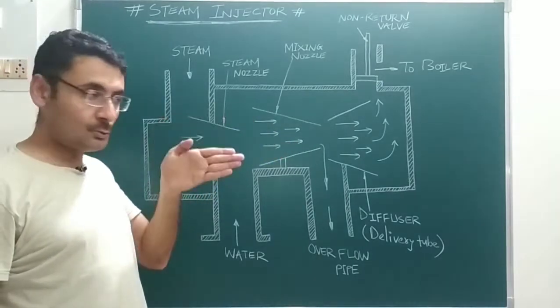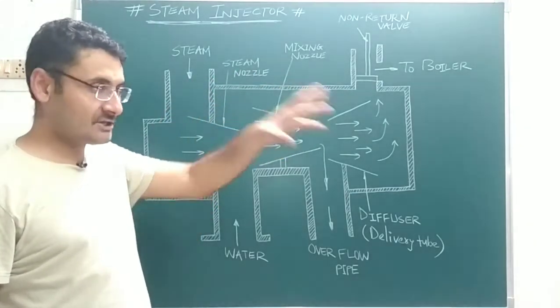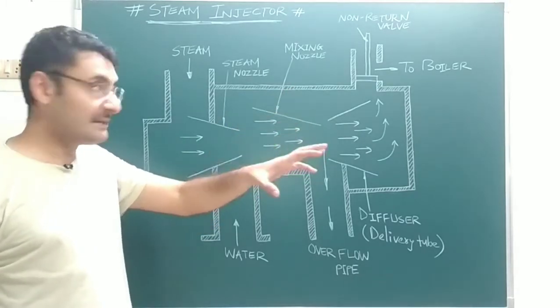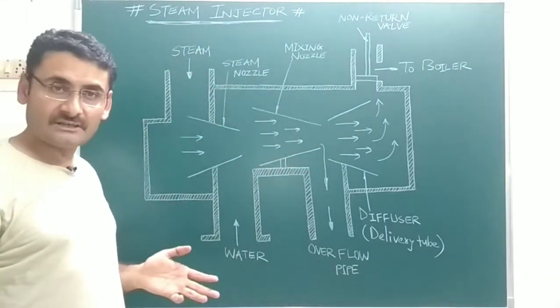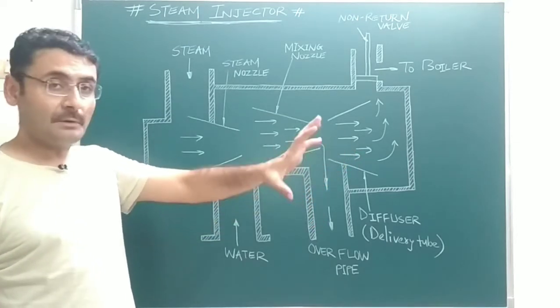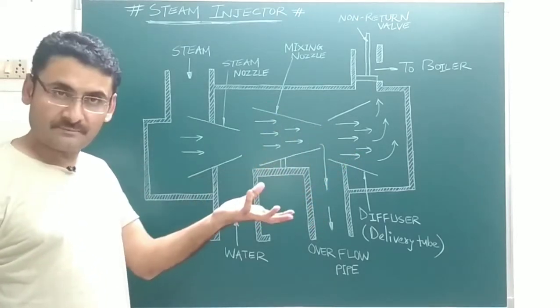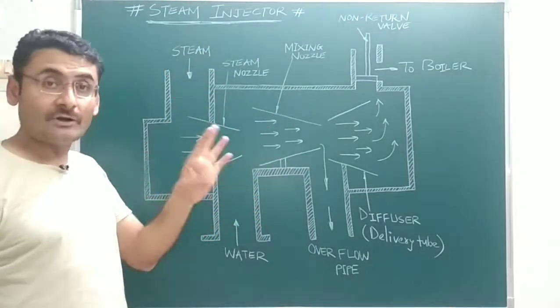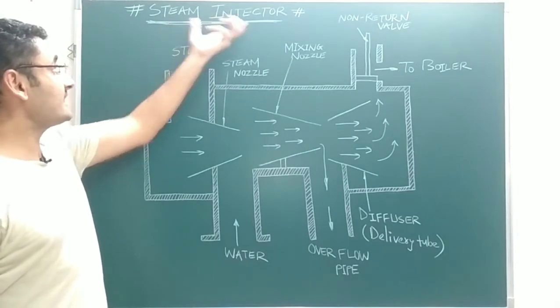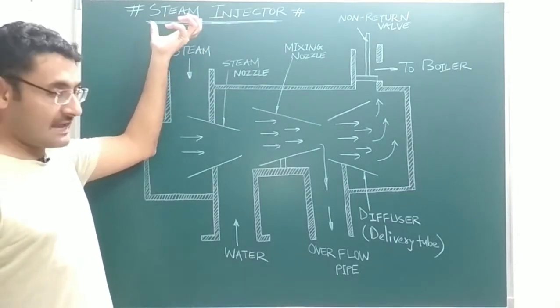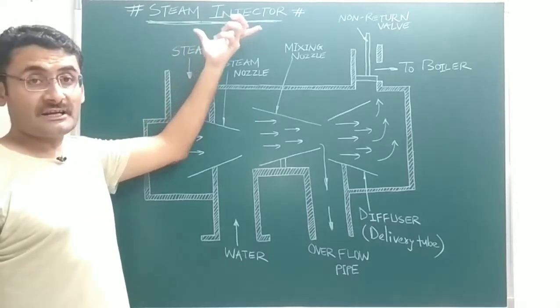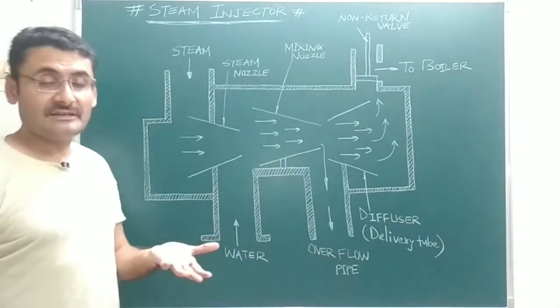Generally, to supply water at high pressure inside the boiler we use a feed pump, but instead we can use a steam injector. A feed pump requires some power to work, but a steam injector does not require any external power — it uses the high-pressurized steam already available inside the boiler, thus saving power.